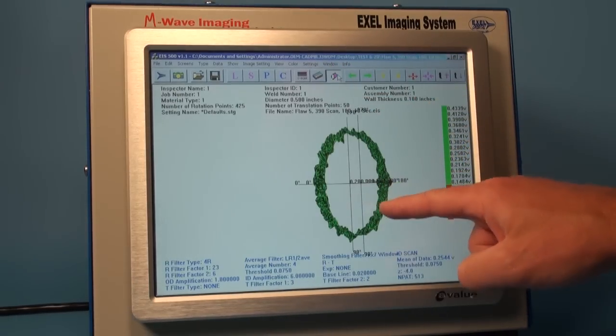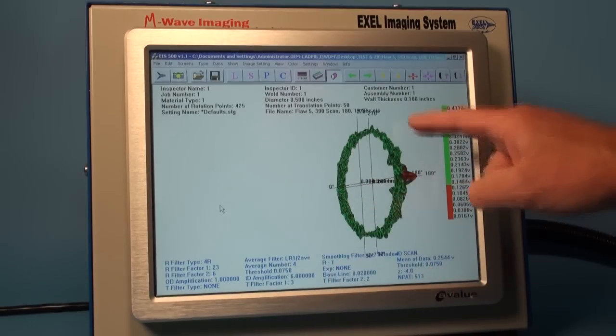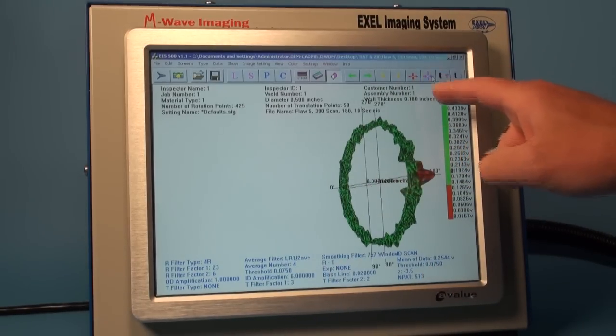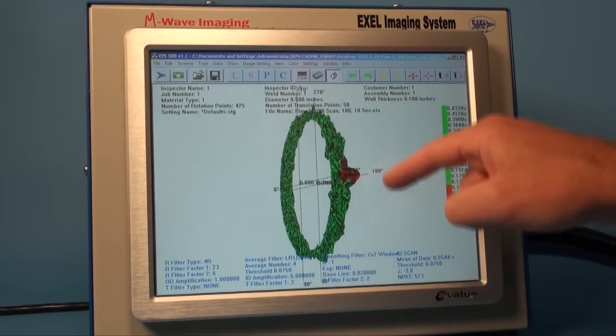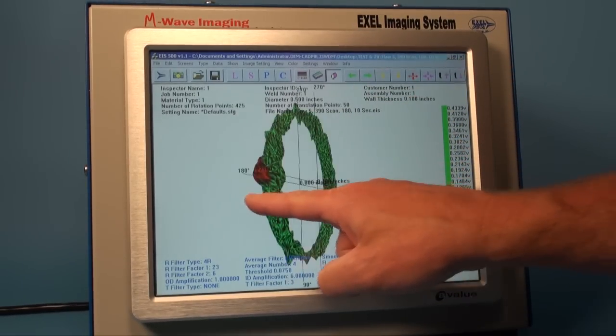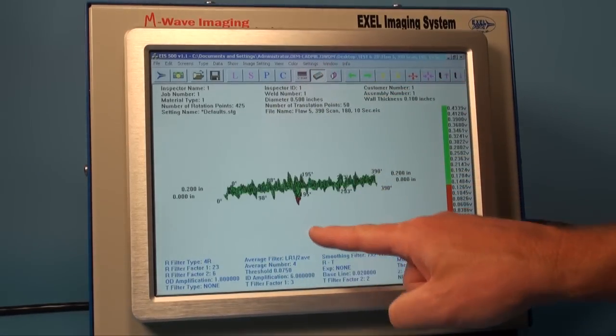The polar view allows the operator to see the flaw as it would appear in the tube. This helps with definitive angular location of defects. Moving to and from different view modes is easy with the touch screen controller.